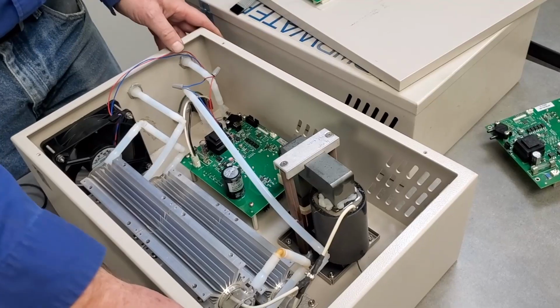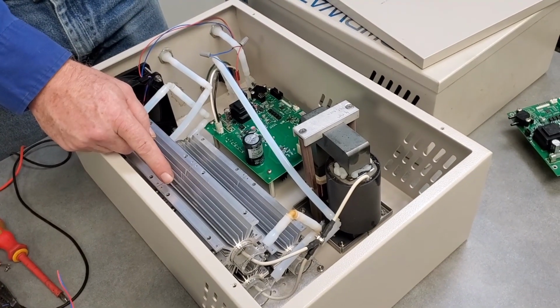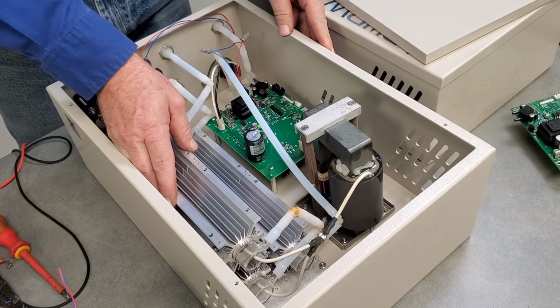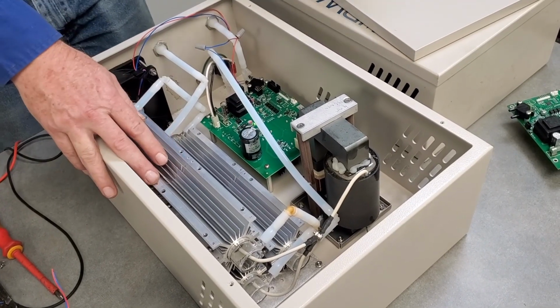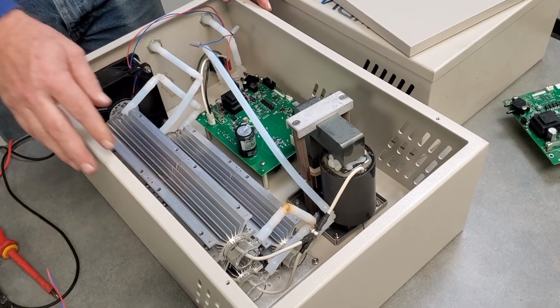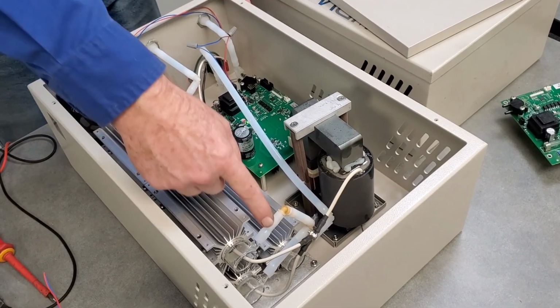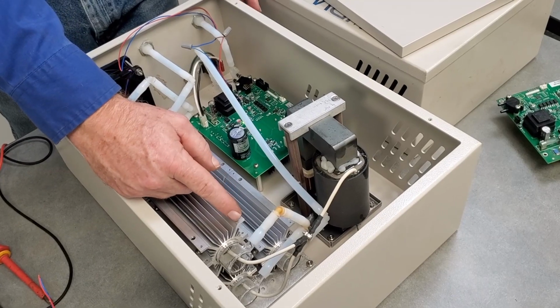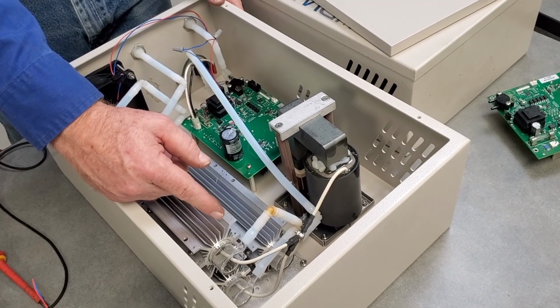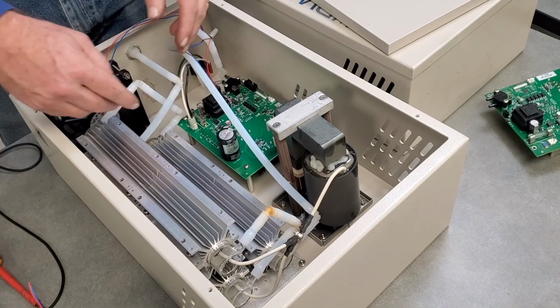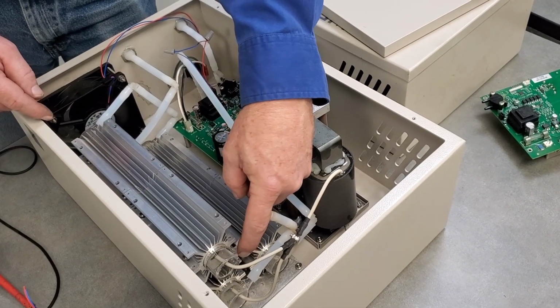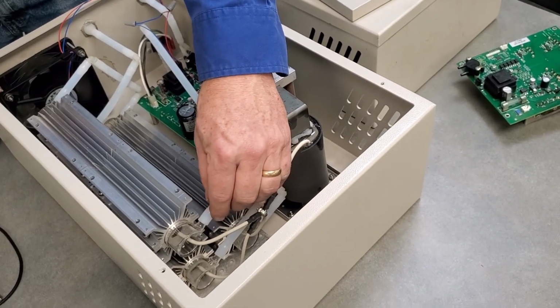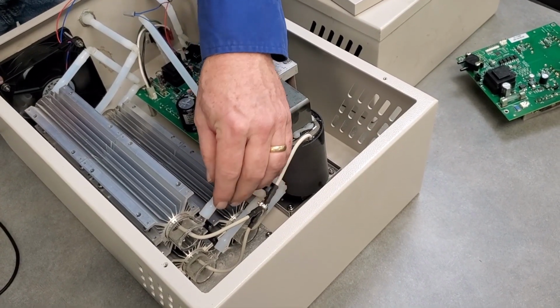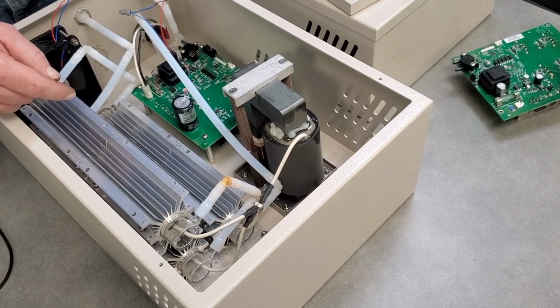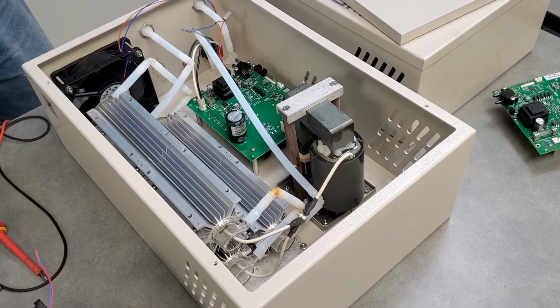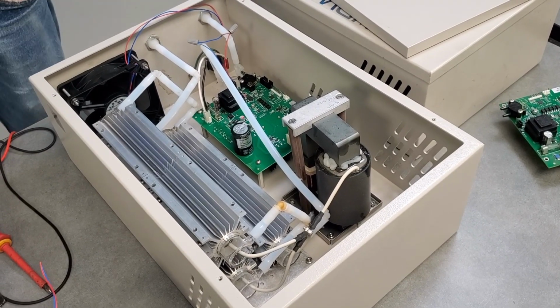Okay, now the last thing that I wanted to show: with these cells, sometimes in transportation when things are really rough, these will move back and forth, and the tubing on here is FEP tubing. It's a rigid type tubing. It holds up really good to ozone. One fault is that it's quite rigid, and it puts too much pressure on these glass nipples, and we see sometimes they get cracked off. And I'll show you how you can take those off and replace tubing if needed.